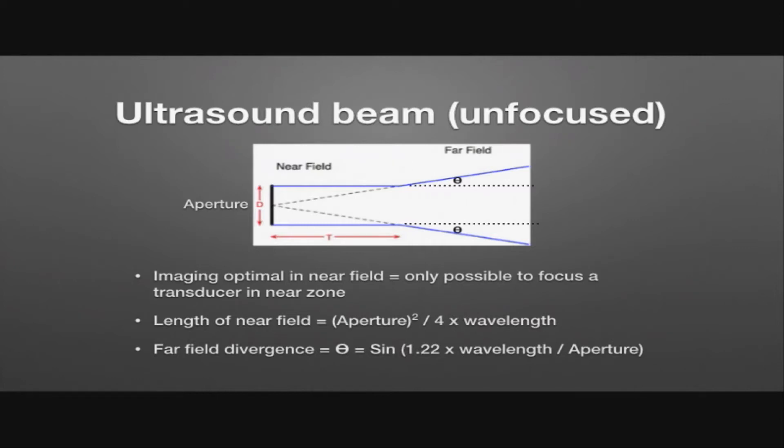Depending on the aperture we can then try and determine what the near field length is, and we can also try and understand what the far field divergence is. And the most important thing to try and understand is that in order to focus the ultrasound beam, we can only do that in the near field. So that's why it becomes very important to try and know the length of this, because that's the area that we're going to be able to improve our resolution when we actually get down to focusing.